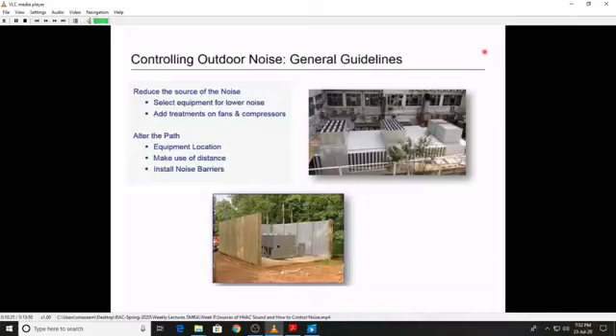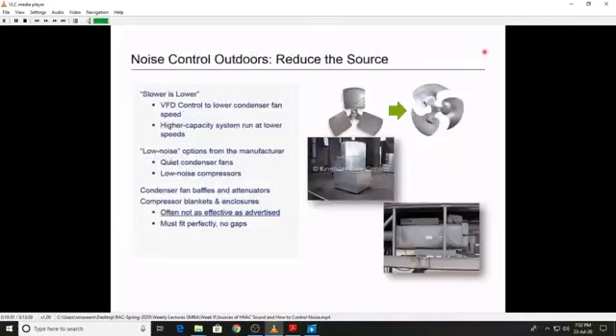Most commonly, what you'll see people do is install noise barriers of some sort around the unit. That can be very effective, but it has to be planned out properly. It has to be executed just right, and it's not always as effective per dollar spent as you might hope. What can you do at the source? Well, always remember one of the most important rules of HVAC noise: slower is lower. If you can slow things down in the system, they will in general make less noise.